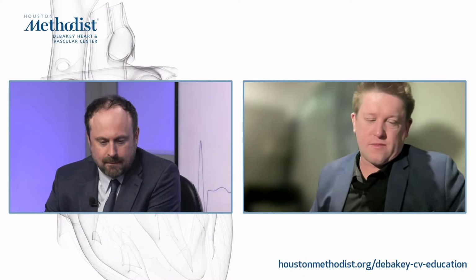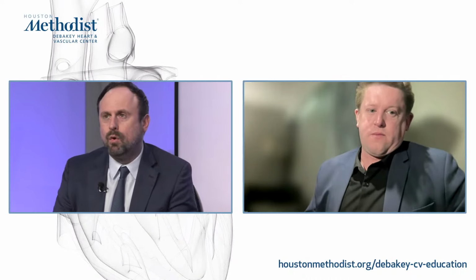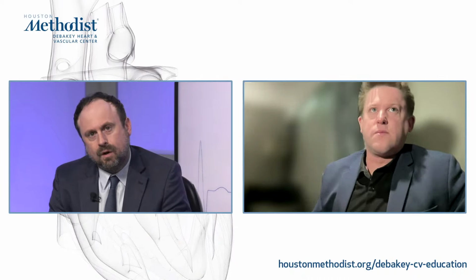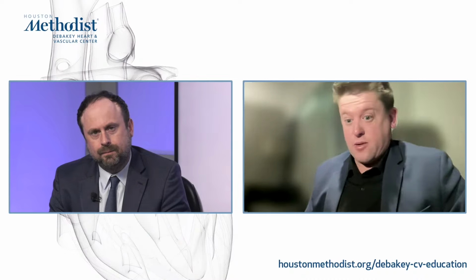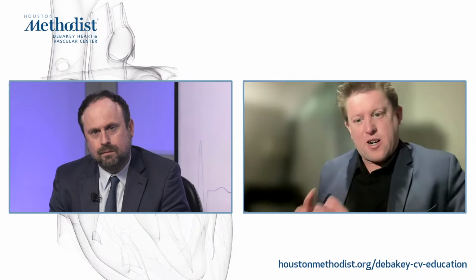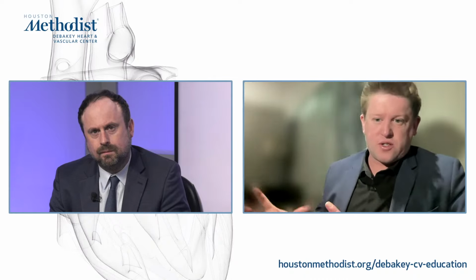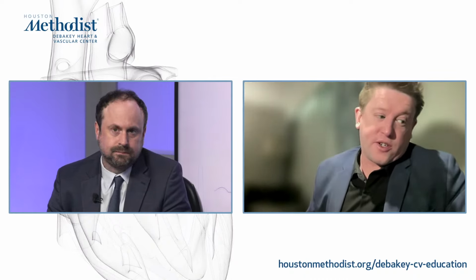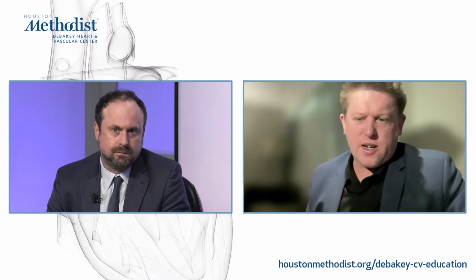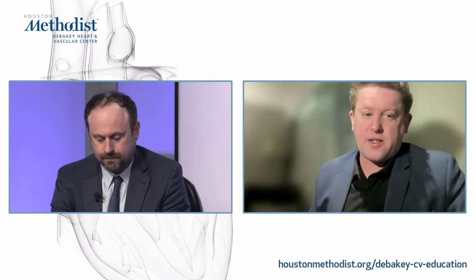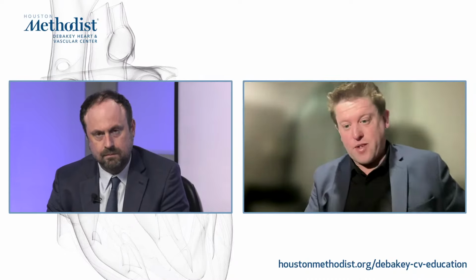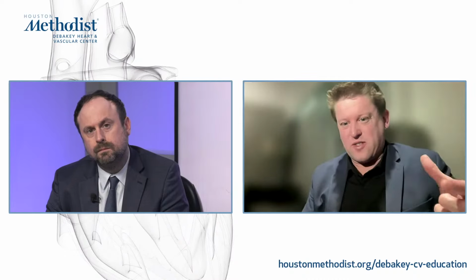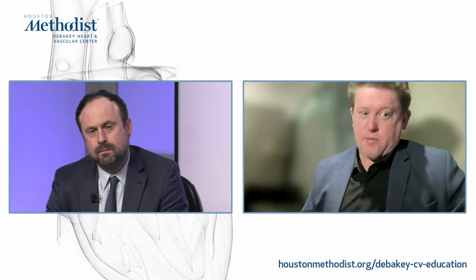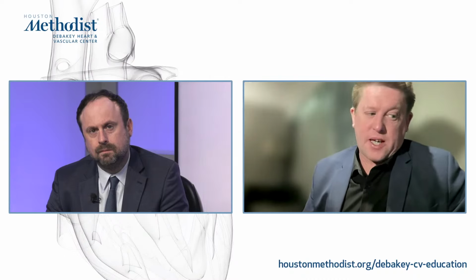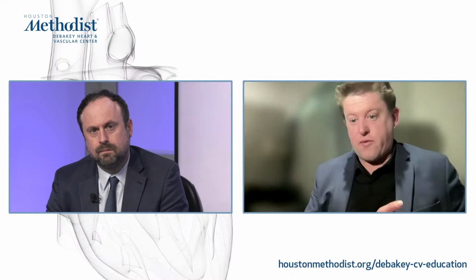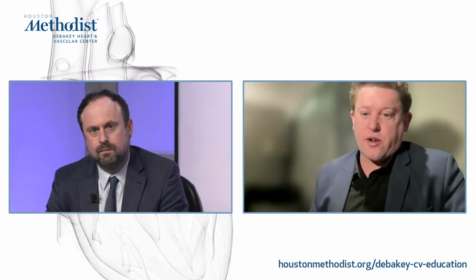Got it, understood. And again, using the bladder as an example, what is the penetration depth of your ultrasound tech? So with the bladder, that was really when we were looking at how deep you can go, because we are operating at higher frequencies, which have attenuation challenges as you go higher. We use a lot of matched filtering and signal processing to recover depth, and with the bladder, I think we're getting about 20 centimeters or so of depth. The use case here was very much toddlers and young children, so the actual depths were restricted. But a lot of the time we look at it on a case-by-case basis, and for the resolutions that we can provide, we are getting exceptionally deep because of the recovery that we can do on the signals.